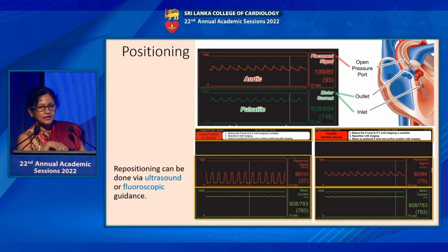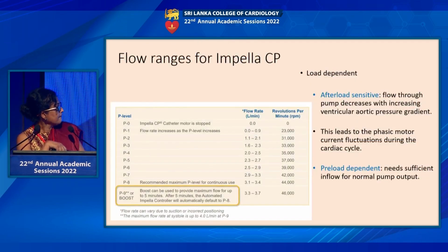So you can readjust it via ultrasound or fluoroscopic guidance. The settings in the Impella are power levels—0 is stopped and 9 is the highest. According to the power level, the revolutions per minute will increase, and for Impella CP, the maximum achievable flow is 3.7 liters.